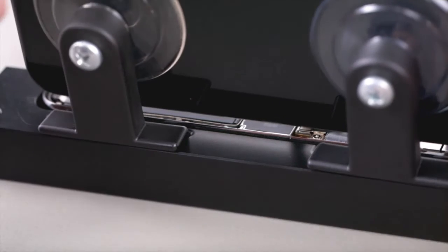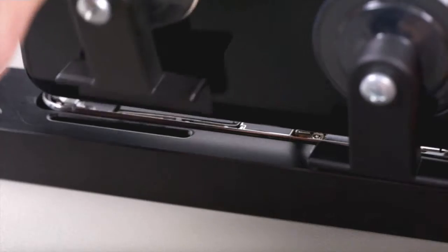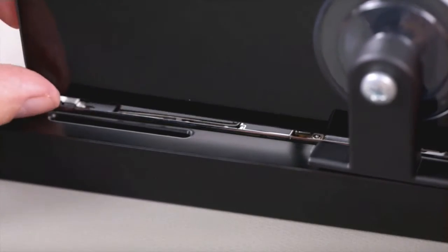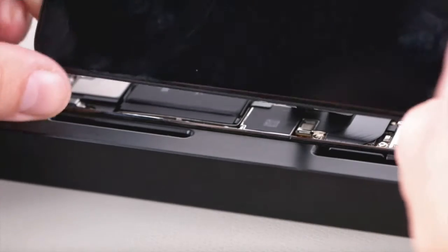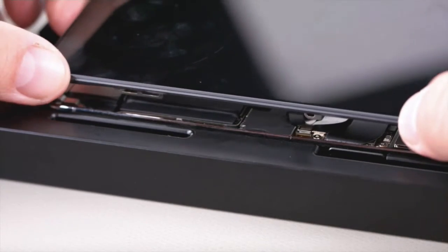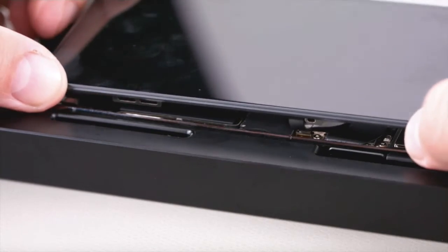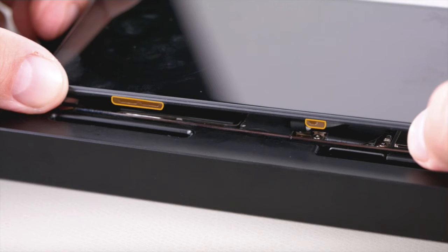Turn the repair tray around. Remove the display from the suction cups. Remove the suction cups. Tilt the display over the enclosure. Check the display clips on the right side to ensure they are aligned.